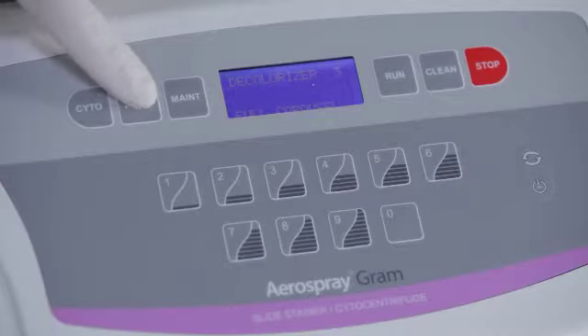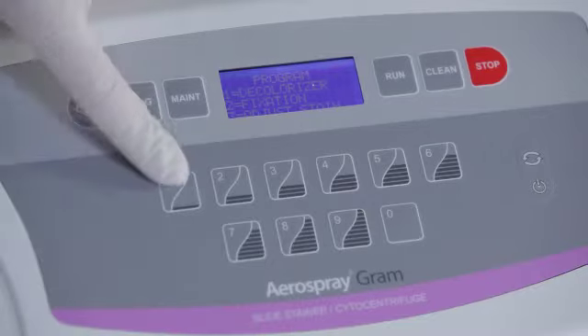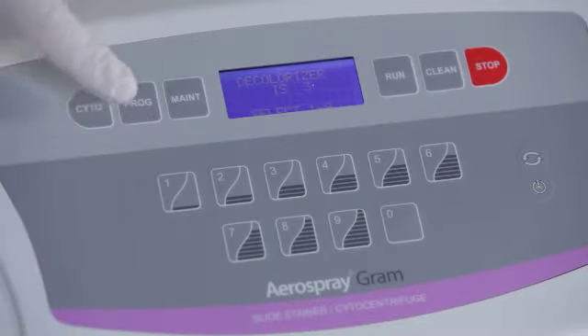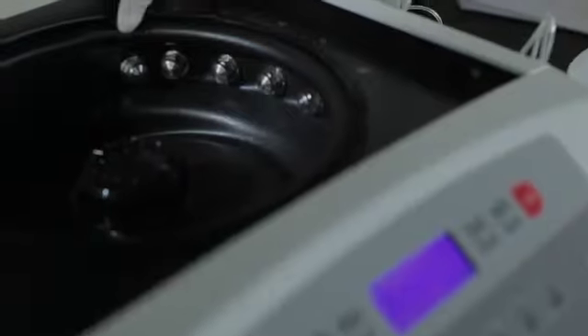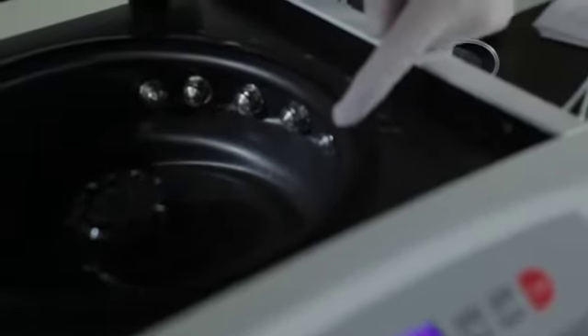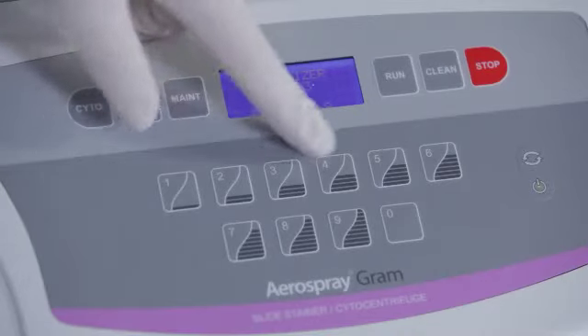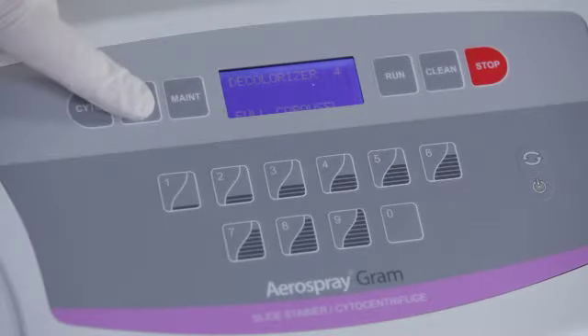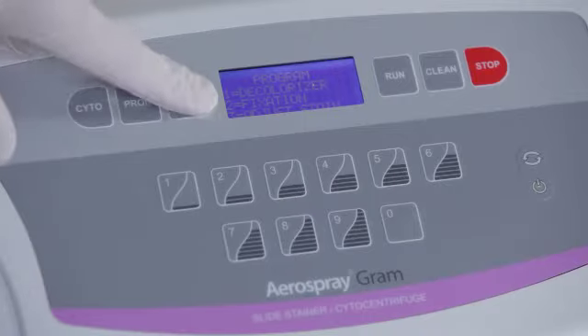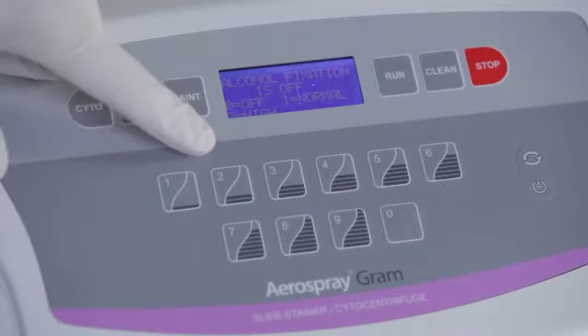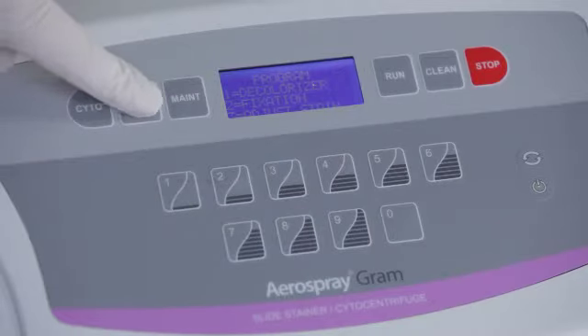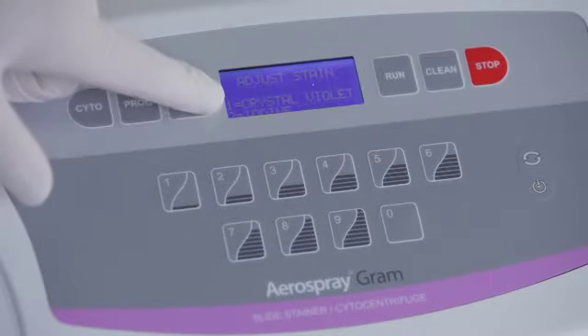The decolorizer settings are changed by pressing PROG and Option 1 for decolorizer setting. Slides can be fixed with alcohol in the stainer, or the fixation can be turned off if the specimen is outside of the stainer. Adjustments for the amount of iodine and crystal violet can be made. The amount sprayed can be set to low, medium, or high. Medium is the default setting. These adjustments are made by pressing PROG and Option 3 for Adjust Stain.